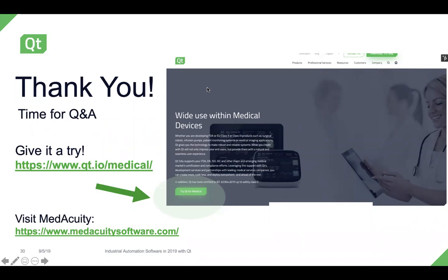But one of the questions here, and I can speak to this on a high level, what happens to the Qt fail-safe, quote-unquote, display when the device hosting is being rebooted? So what is rendered in the safe renderer will be displayed on the screen still. So imagine a heart rate and a respiration rate. Let's say those numbers you actually rendered in the safe renderer, they're still going to be on the screen and they're still going to be accurate. And that's what the certification to 62304 and 61508 speak to, that it will not only still be displayed, but the numbers that are there are going to actually be someone's heart rate or respiration rate.